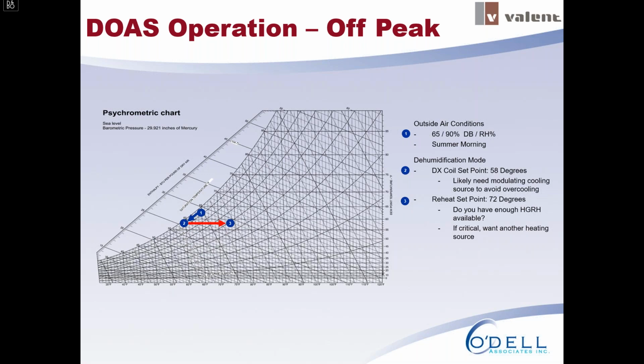Well, you're going to have a DX coil set point that you have to get down to. And to do that, you're going to need some sort of modulation. If you run your compressors at full capacity, they're going to overshoot and overcool, and you're going to end up turning compressors on and off, and your supply temperature is going to fluctuate wildly. And that's not what we want. We want a nice, even supply temperature. We want to be able to modulate.